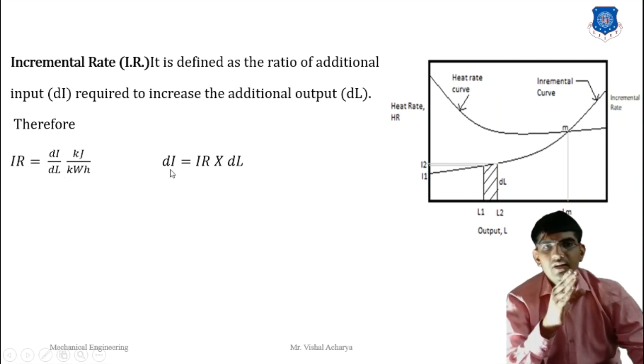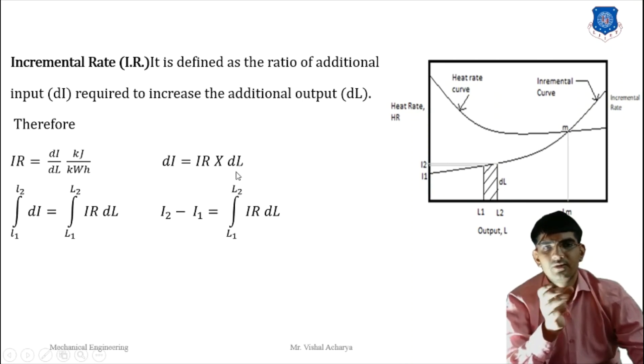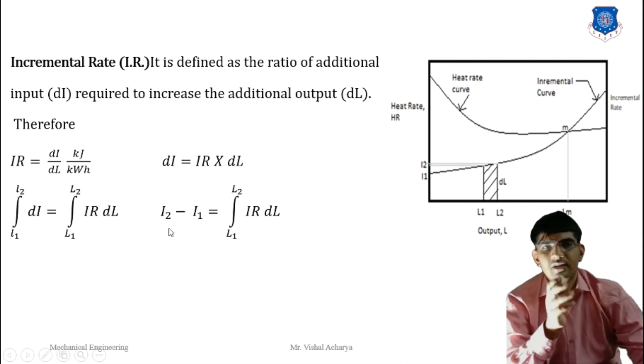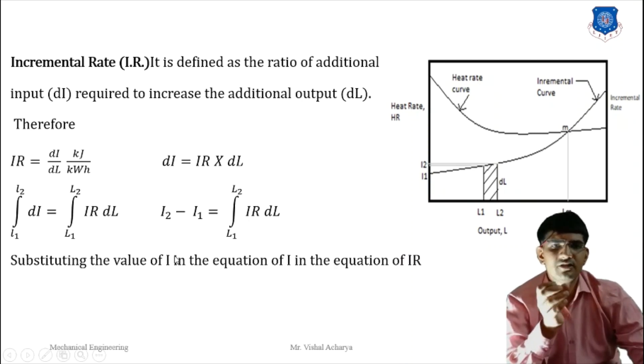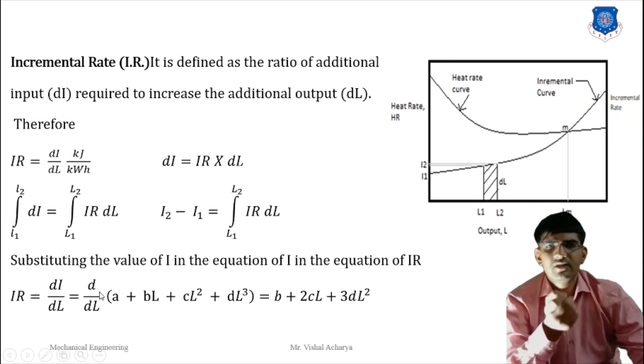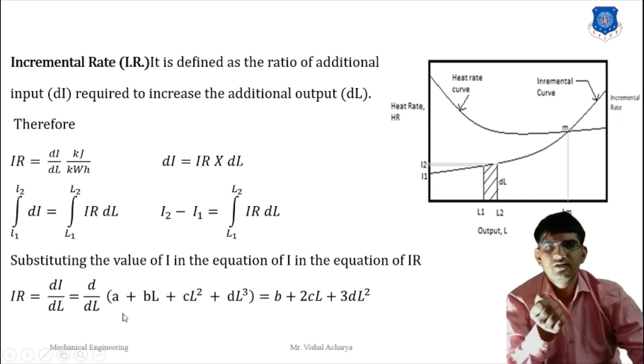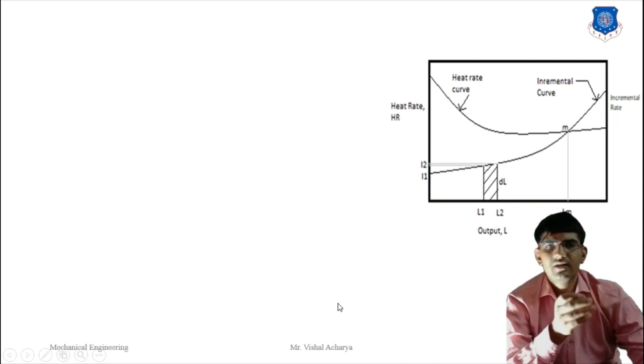Increased input equals incremental rate multiplied by increased additional output. Integrating both sides with limits I1 to I2 for input and L1 to L2 for output, we get: I2 − I1 = integral from L1 to L2 of (dI/dL) dL. The incremental rate = dI/dL. Given input I = A + BL + CL² + DL³, differentiating with respect to load: dA/dL = 0, d(BL)/dL = B, d(CL²)/dL = 2CL, d(DL³)/dL = 3DL². Therefore, incremental rate = B + 2CL + 3DL².